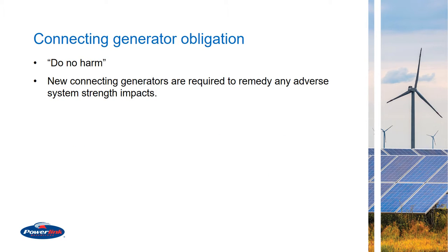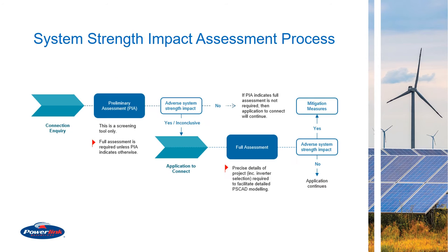Generator has an obligation to do no harm. What it means is that when a new generator connects to the network, it must not adversely impact the performance of any existing plant connected to the network. It also has a responsibility to provide system strength mitigation if the system strength assessment done by the NSP concludes that a new connection is causing adverse system strength impact.